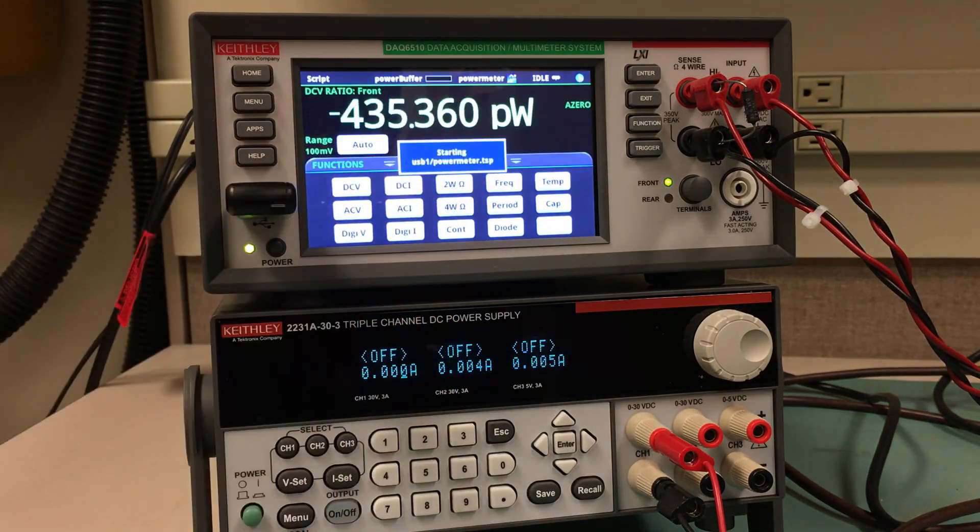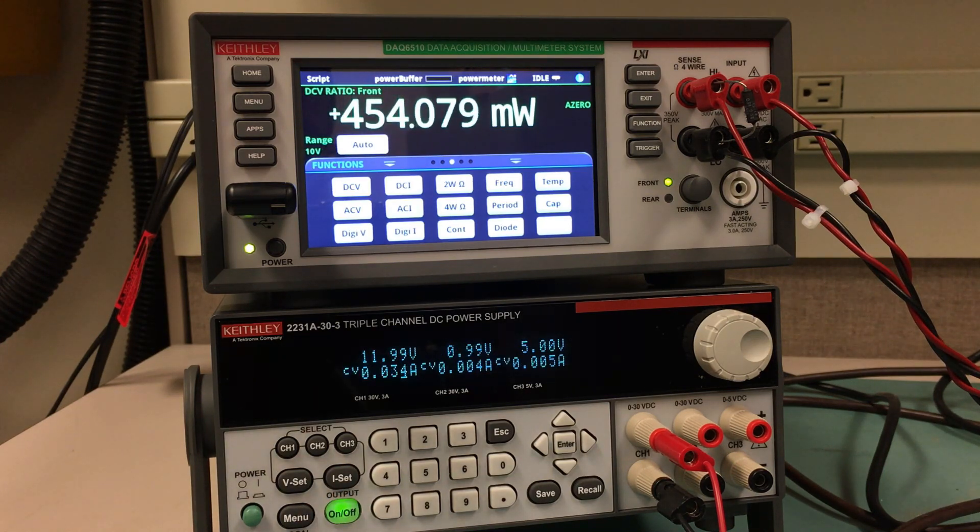With the help of some TSP scripting, we can get the results shown here. We will go into more detail about how the script works in the second half of this video. We can actually show the power measurement live on screen with watts as units. TSP allows the instrument to do all the necessary math to display power. The script being run is available below.